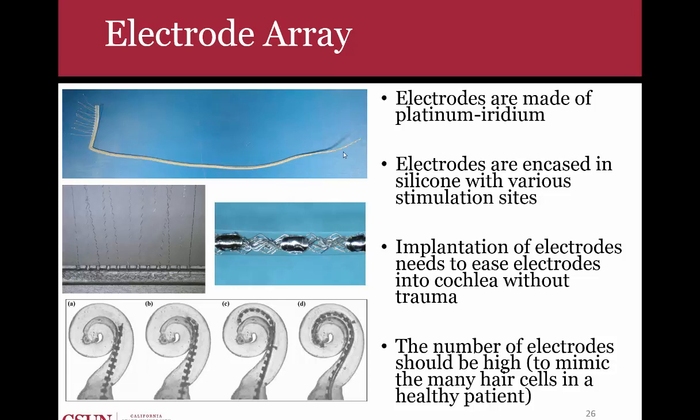So at the top here are the electrodes that are going to be sitting in the cochlea, and these are all the leads. They're individual wires that are connected to the implant, where the RF link sends the stimulating pulses. So each of these wires is effectively a given pulse. In this case, there's 1, 2, 3, 4, 5, 6, 7, 8, 9, 10, 11, 12 electrodes.